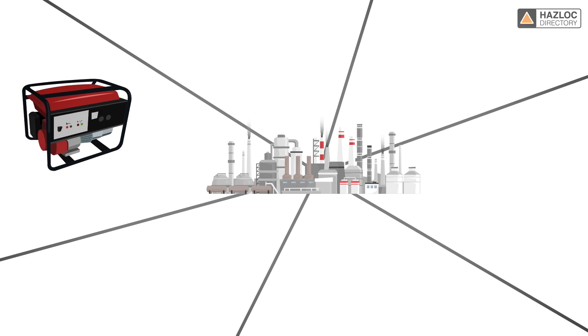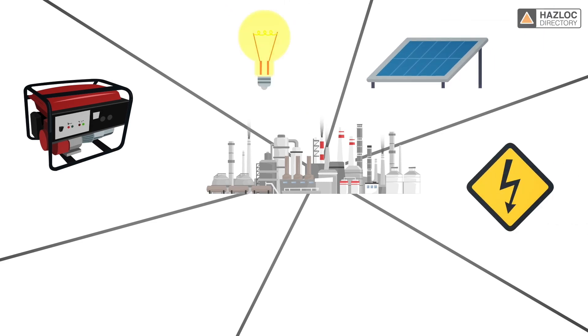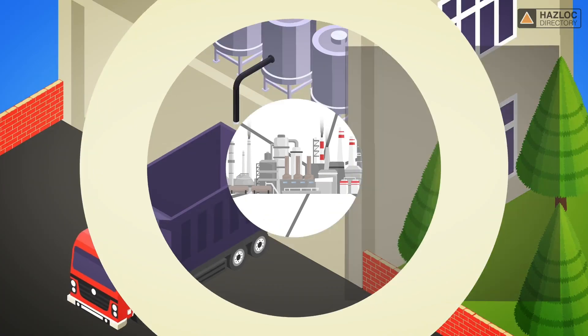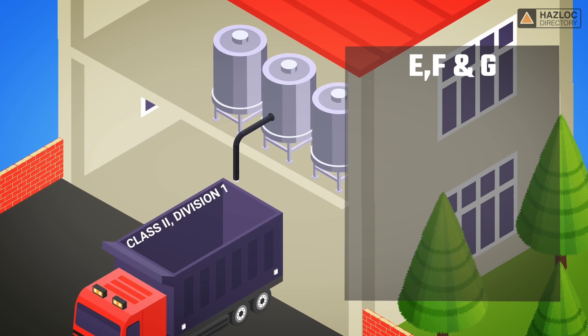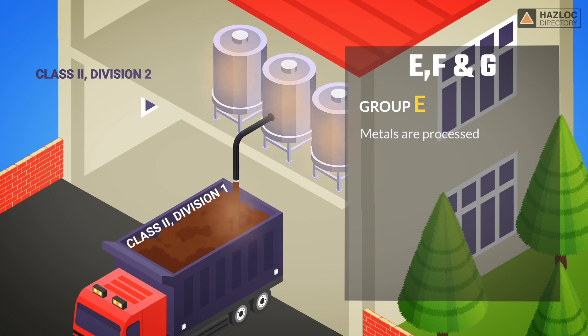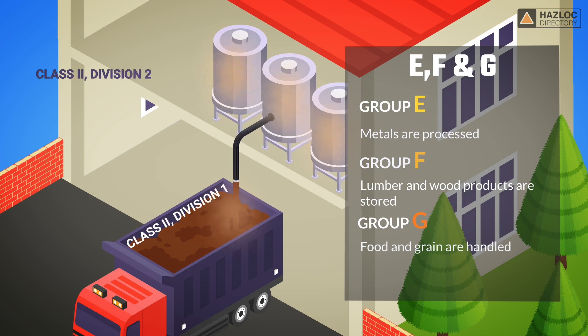Electrical equipment is often installed in locations where there are explosive dusts present. Dust is further classified in three groups in North America. Dust Group E, electrically conductive combustible metal dust, may be found where metals are processed. Dust Group F, combustible dusts other than metal, are found where lumber and wood products are stored. And Dust Group G, solid particles including fibers, may be found where food and grain are handled.